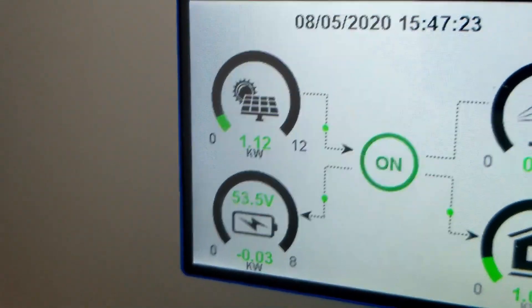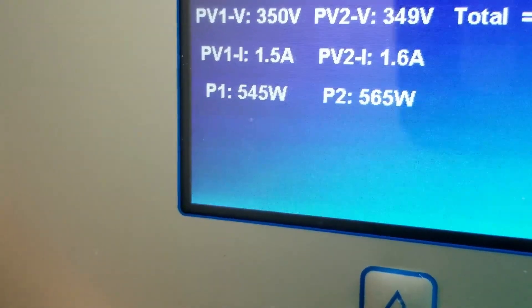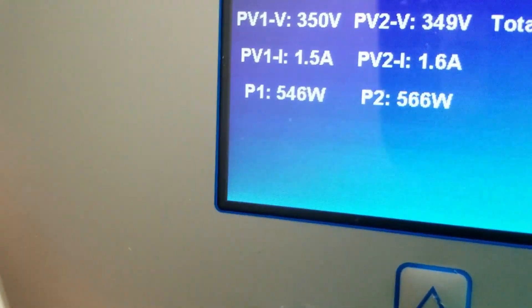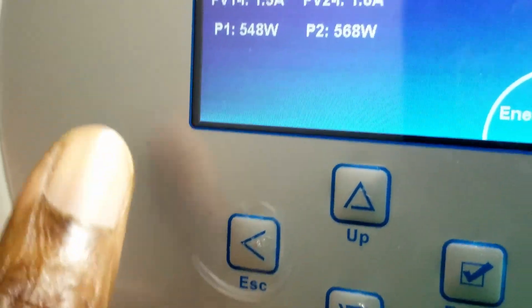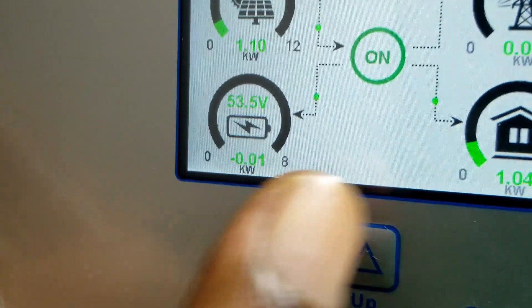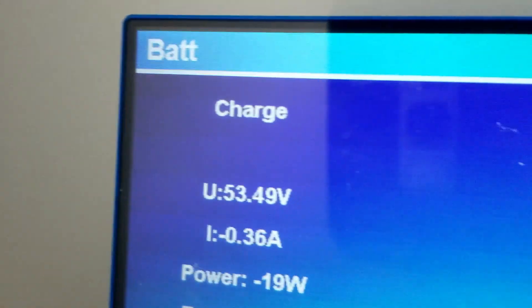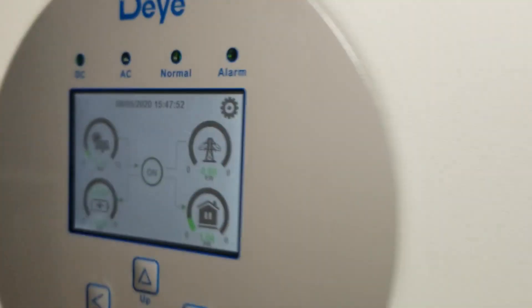Let's see what this is doing. Right now he's producing 1,112 watts. He's done 8.7 kilowatt-hours. There is no grid — the grid has not been here for the last four days. His consumption is so low right now that that's all he's producing. He's consuming 1,042 watts, so he's matching what he's consuming. The batteries are in float, as you can see.